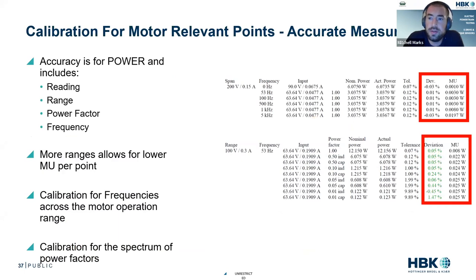I will not belabor this or walk through this at great depth, but HBK does calibration for motor relevant points to ensure you have the most accurate measurements for where your motor actually operates. So one, we calibrate on power. Not everybody does this. Some people just calibrate on voltage or current. You need to calibrate on power because it's a multiplication, but it has to do with the phasing between the channels. You cannot just assume an uncertainty.